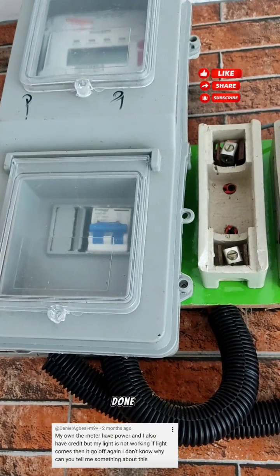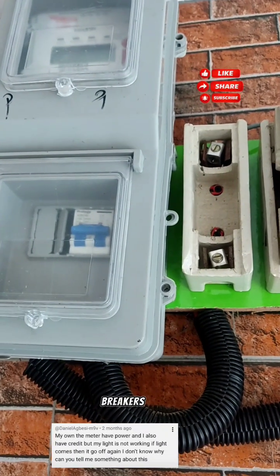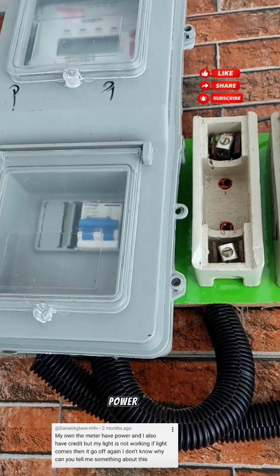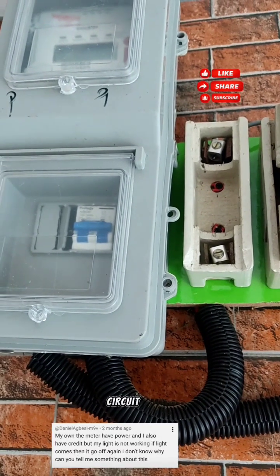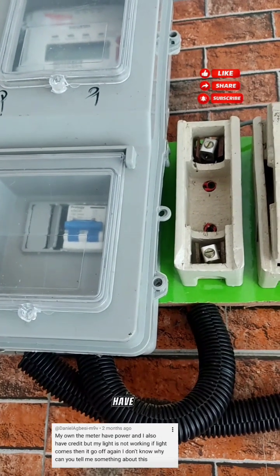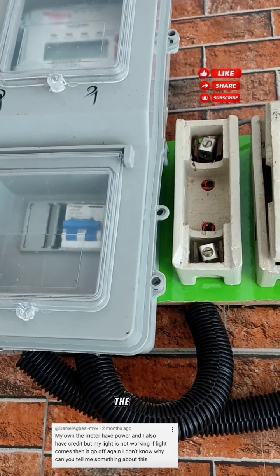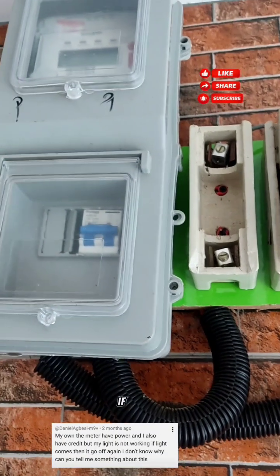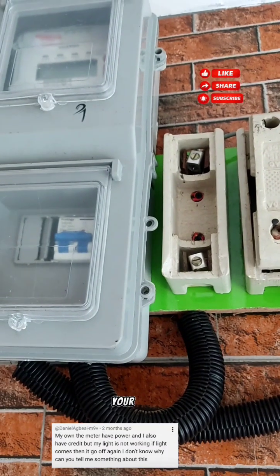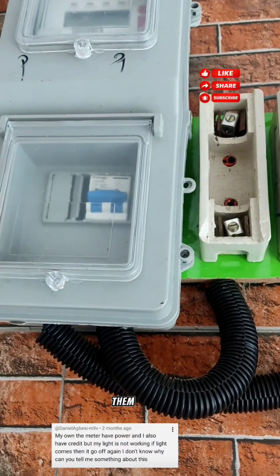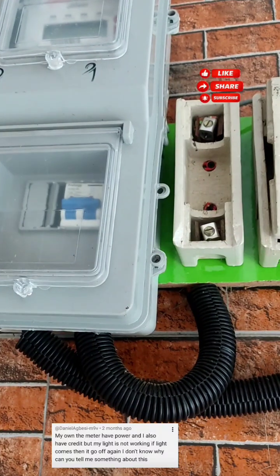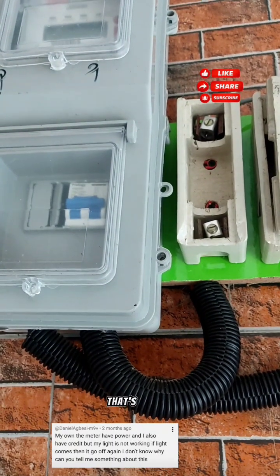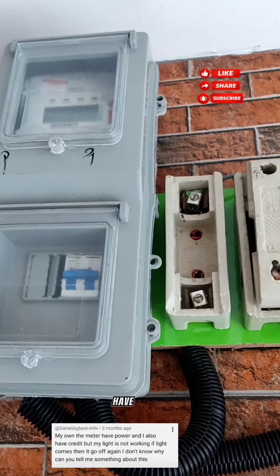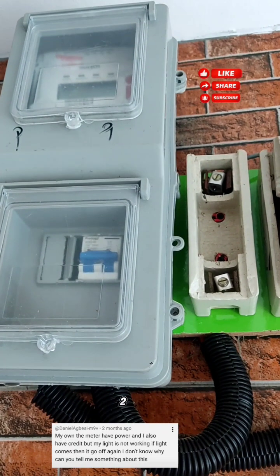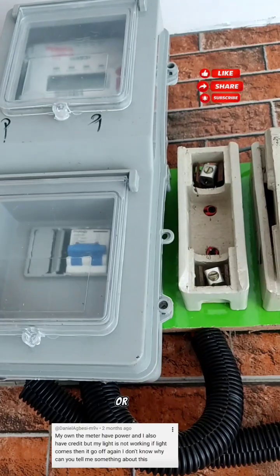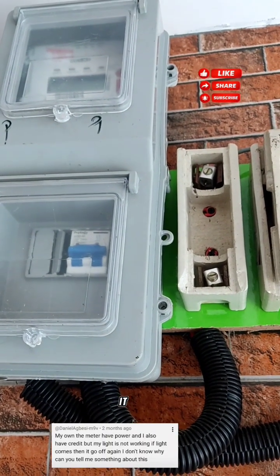Then, when that is done, next you switch on the individual breakers one at a time. If the power goes off after turning on a particular circuit, you have likely found the faulty circuit or appliance. So if you have, say, six circuit breakers in your house, you switch them on one by one until you get the one that will trip off. That's how you troubleshoot and find the area where you have the short circuit or the fault. Two, check whether the breaker on the meter or distribution board has tripped and reset it if applicable.